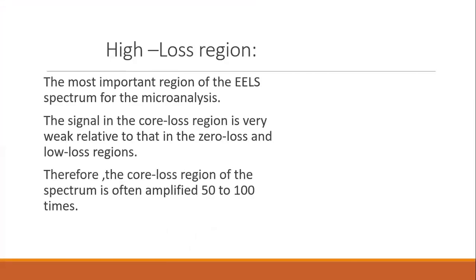High loss region is the most important region of the EELS spectrum for micro analysis. The signal in the core loss region is very weak relative to the zero loss and low loss regions. Therefore, the core loss region of the spectrum is often amplified fifty to one hundred times.